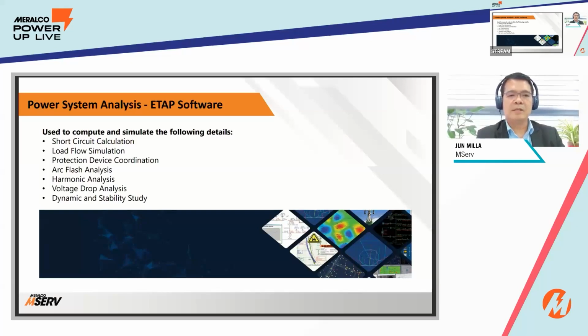Power system analysis, this is the one I told you MServe had, an ETAP software. So what is this ETAP software? It could be used systematically to provide equipment sizing, short circuit calculation, load flow simulation, protection device coordination, arc flash analysis, harmonic analysis, voltage drop analysis, and dynamic and stability study. All this could be completed using the ETAP software.